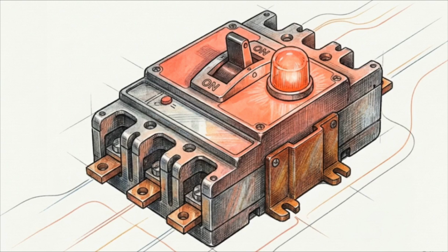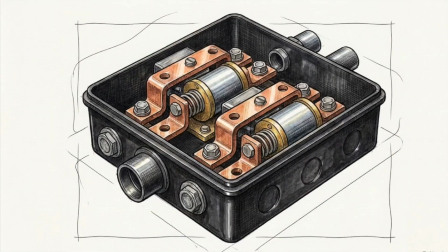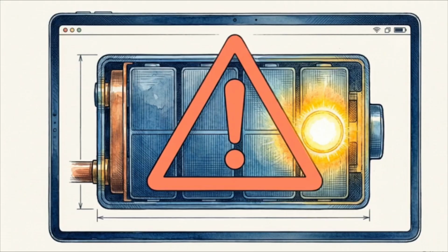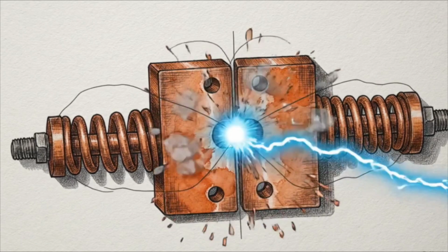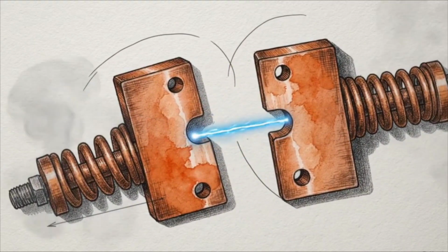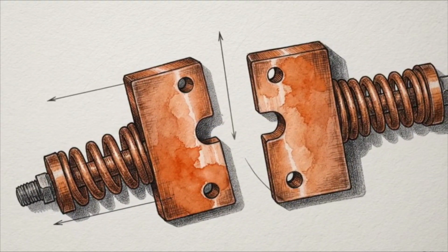Calculating limits is only half the job. The BMS must have a way to physically intervene if the battery breaches those limits. This physical intervention relies on heavy-duty, high-voltage contactors, mechanical relays physically housed back inside the battery junction box. If the BMU detects a severe fault condition, like a sudden voltage spike or rapid temperature increase, it triggers these contactors to physically snap open, instantly severing the connection between the battery pack and the outside circuit.